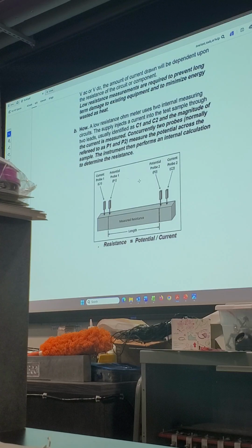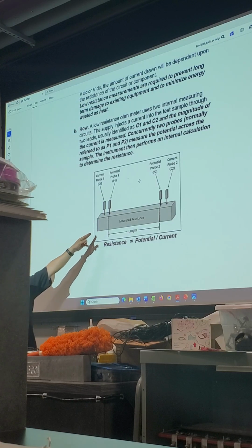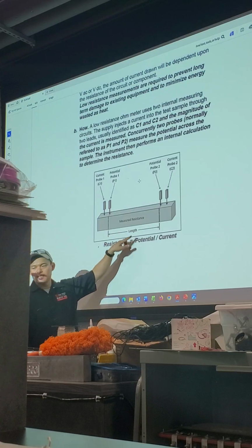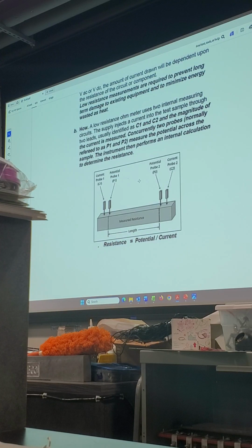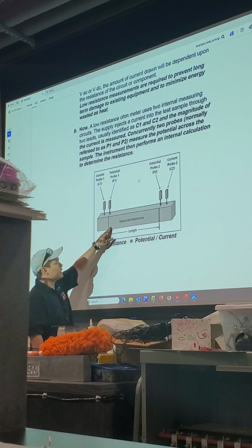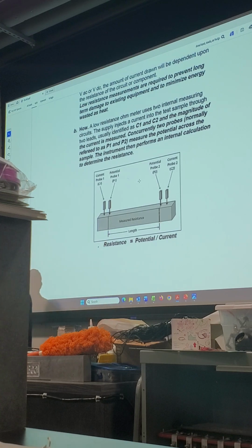They don't show the DC supply. They don't show the ammeters and voltmeters that were pointed out for us. But in this case, we are seeing where C1, P1 made contact and C2, P2 made contact, and we know that it is directly across the subject. We know that these made contact here because the calculation is only performed here. Anything upstream of that, aka the internal resistance of the leads, doesn't matter. They could be short leads or they could be long enough to go to both ends of those transformers in the yard. However long those leads are, we only care about the resistance across the piece of equipment the customer is interested in, the one he laid out before you.